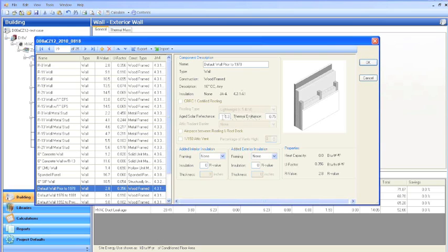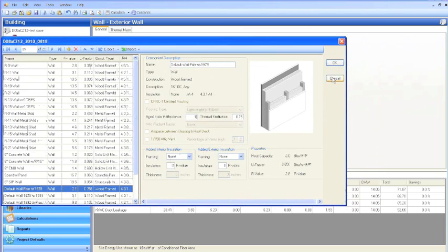solar reflectance. If it's an interior wall, then what you are going to say about it is that it has a solar reflectance of 1. What that means is no sunlight or no sun heat is coming through that wall. It's a knee wall. It's going into your attic. The sun isn't hitting it directly. So that part of that wall is not subject to heat coming in from direct sunlight. And so that's how you would enter in that bit for a knee wall.